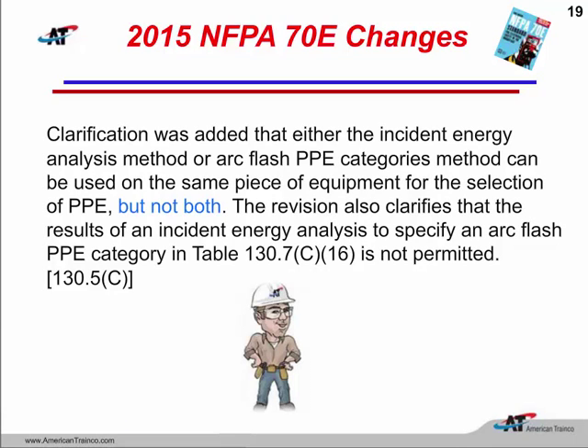Okay, so here's a major change I want to say that, and this has been in 70E for as long as I can remember, since the 2004 edition, and they have stressed it at technical committee meetings, they've stressed it at seminars, but the document itself really had to be rewritten a little bit so that we can understand that there are 2 ways to apply a label to equipment. We can use the incident energy analysis, or we can use the PPE category method. Okay, so we have 2 choices here.